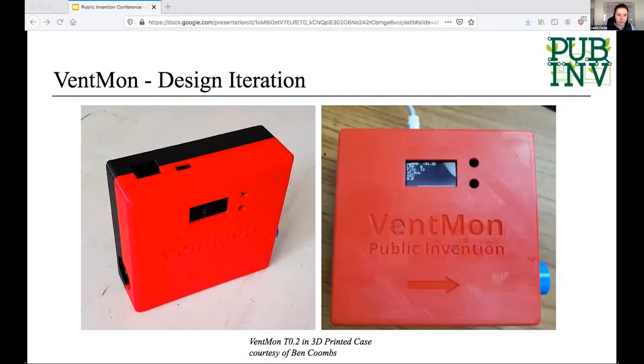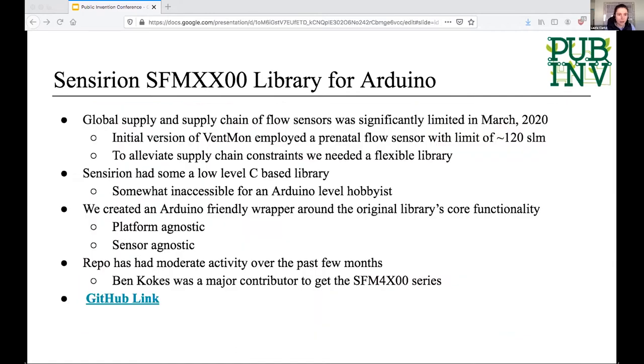I'm going to talk super briefly about one of the critical components in all these ventilator devices: the flow sensors that measure actual air flow. The global supply chain for flow sensors was significantly limited in March, and this was something we identified pretty early on as a problem we needed to solve. For example, the initial VentMon that we built used a neonatal flow sensor which has a very tiny hole and was really hard to breathe through for an adult.